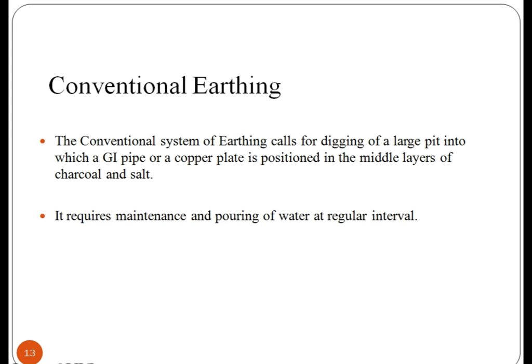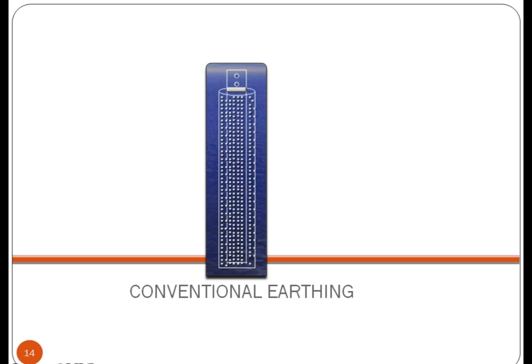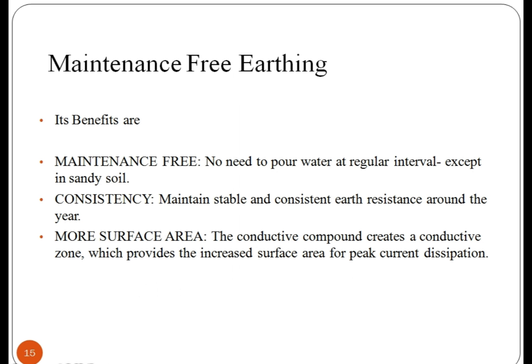The conventional system of earthing calls for digging of a large pit into which a GI pipe or a copper plate is positioned in the middle of a layer of charcoal and salt. It requires maintenance and pouring of water at regular intervals. You can see the conventional earthing diagram which shows the earthing mechanism. Another type of earthing is maintenance-free earthing. It is a new type of earthing system which is ready-made, standardized and scientifically developed.